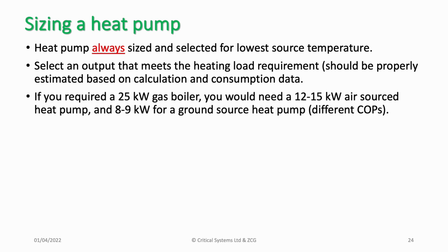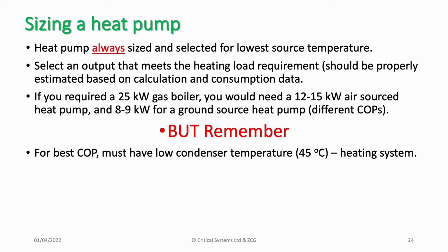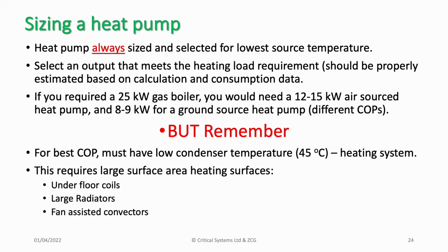Now, if you required in your existing property, say a 25 kilowatt gas boiler, you would probably need a 12 to 15 kilowatt air-sourced heat pump and an 8 to 9 kilowatt ground-sourced heat pump based on the different coefficients of performance. But remember, for best COP, we must have low condenser water temperature, that is in our heating system, and the maximum flow temperature should be around 45 degrees centigrade. Now, this will require a large surface area of heating surface in your property. Ideally, a heat pump system will use underfloor coils, but you may also use large area radiators and fan-assisted convectors.